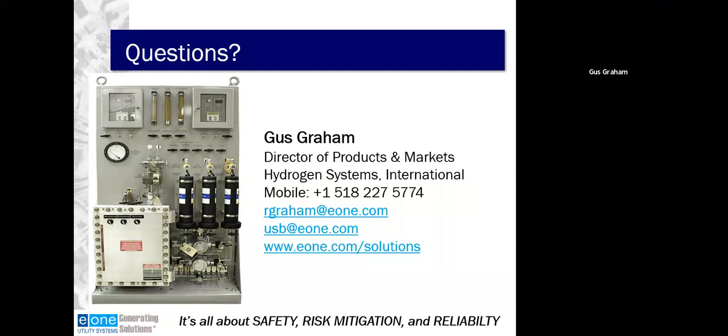Yes. So eOne's approach to that is that we have a cell block heater that's part of the thermal conductivity cell. What we do is we elevate the temperature of the gas above the ambient temperature, and that enables us to eliminate the ambient temperature effect on the gas sample, to ensure an accurate response across all ambient temperatures.